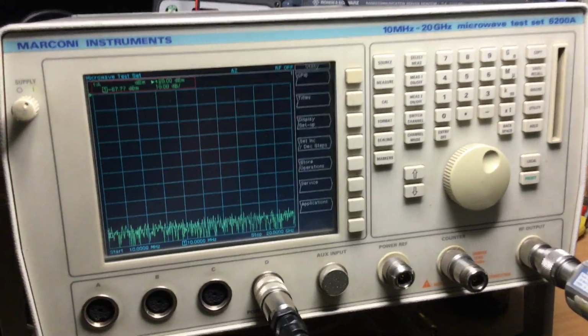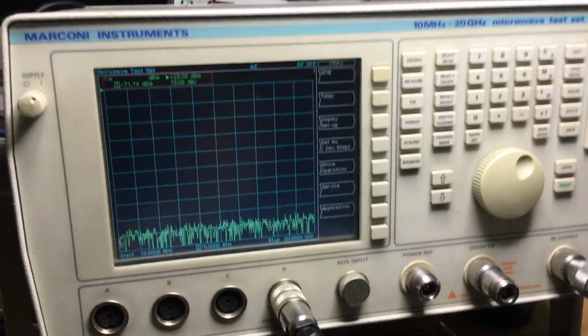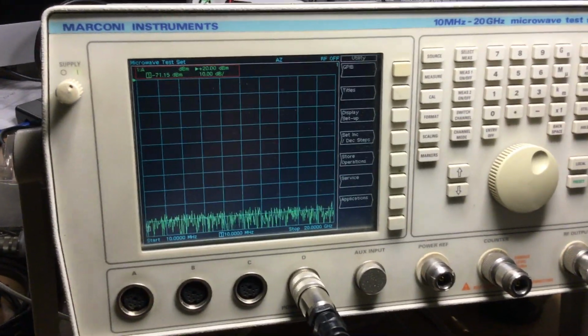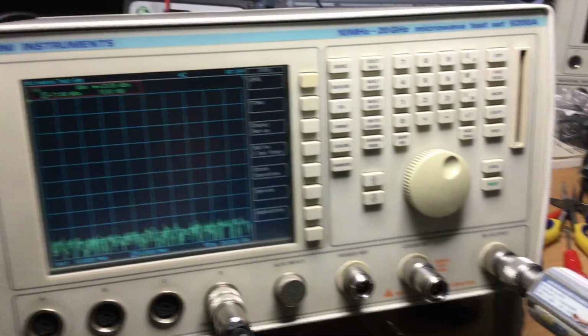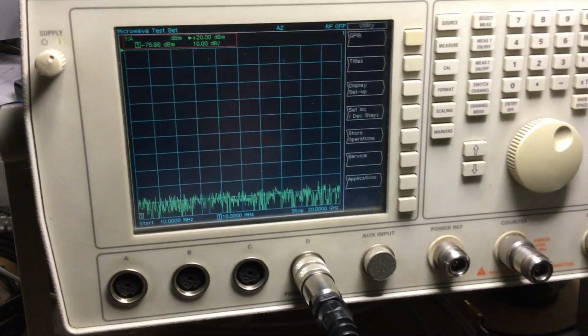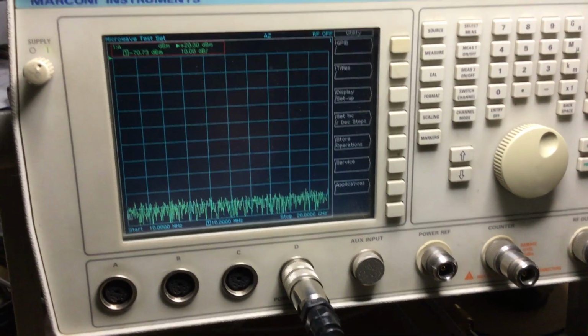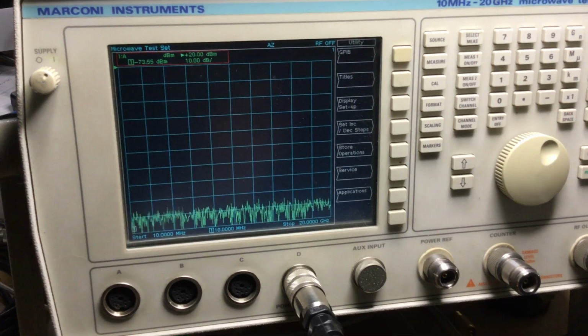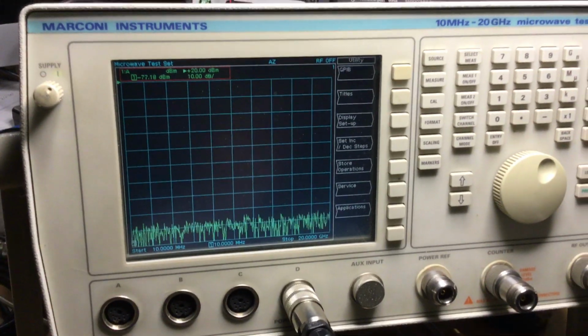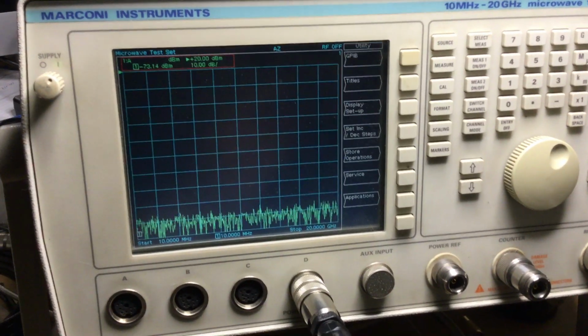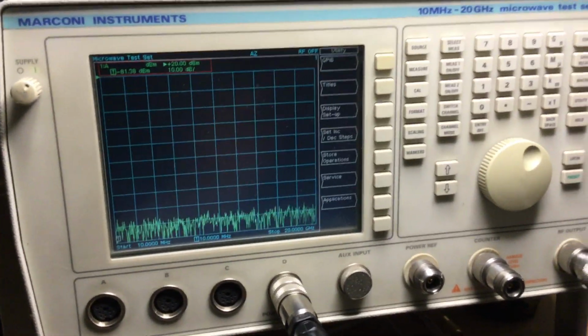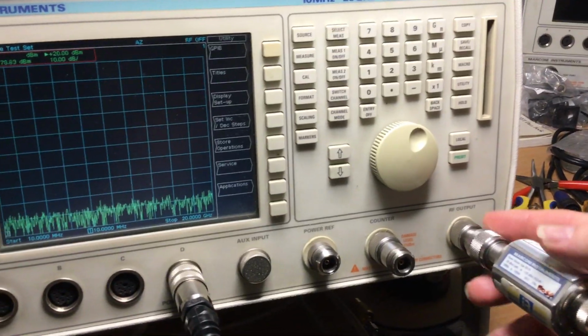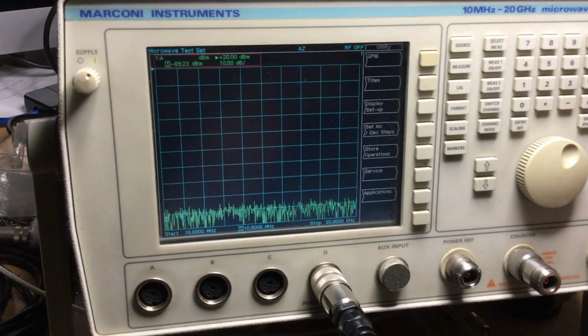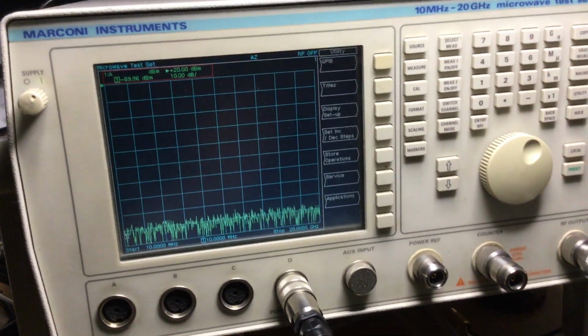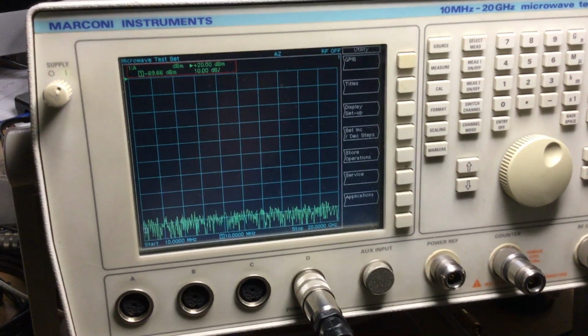Hello there, thank you for joining me again on the instrument calibrations part of the Marconi microwave radio test set. In the previous video we looked in the service menu and the diagnostics, and showed the ALC DAC value being adjusted, which represents what the pick-off diode sees, internal within the RF output section of the test set. We're going to try and do an instrument calibration.